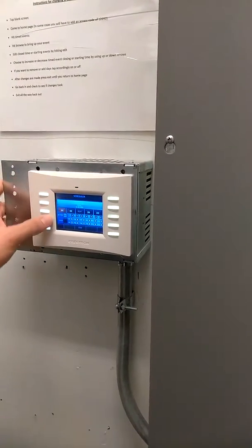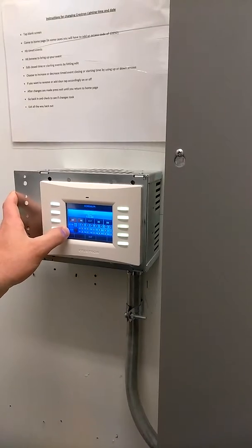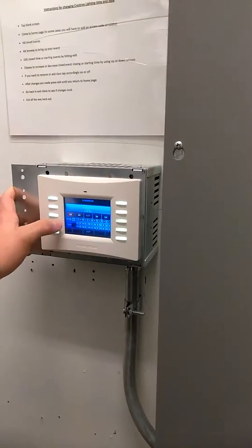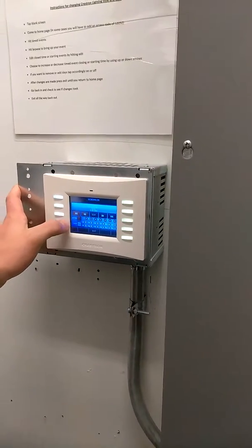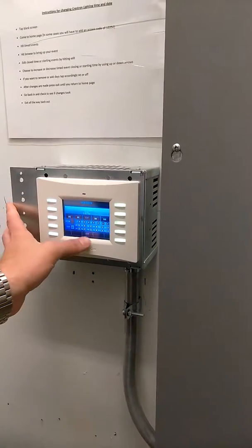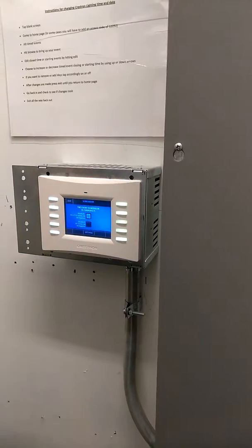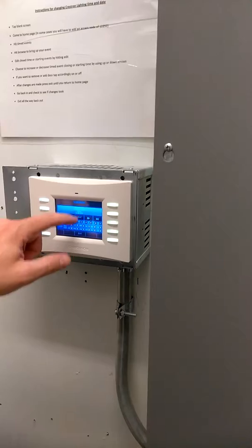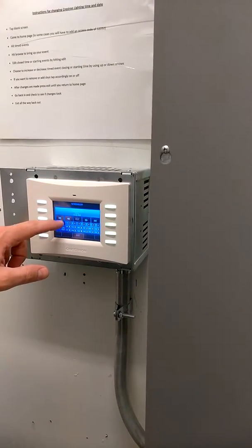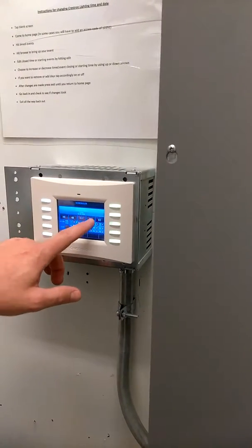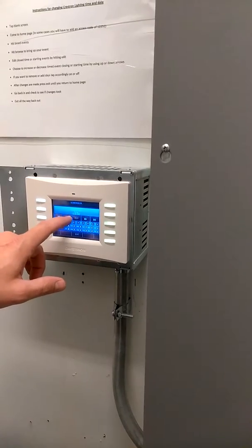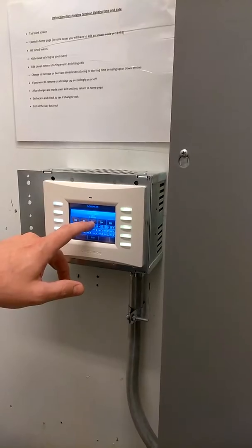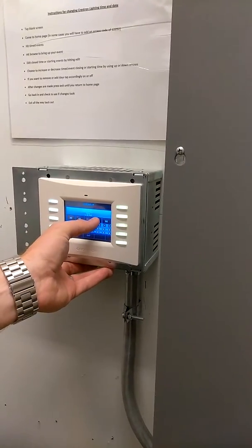The important thing about the events are the active and suspended options here. So this event is active. If I wanted to suspend this event, I hit suspend, and I can hit exit, and that event will forever be suspended. So this event called Building Open will never fire because it's suspended. I'm going to leave this active. You can scroll through your events using the navigation buttons, and when you want to edit the event, you can hit edit. So let's go to the next event.